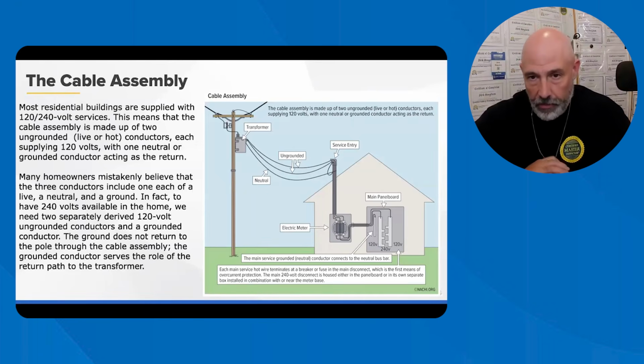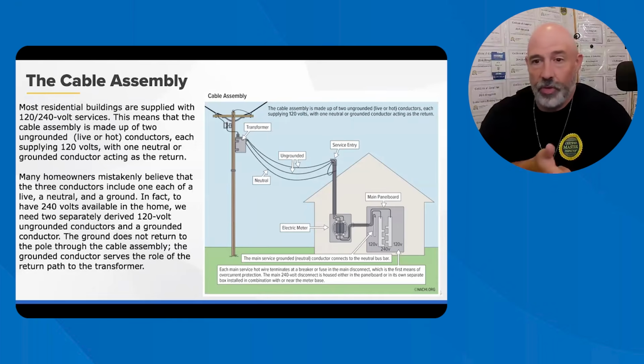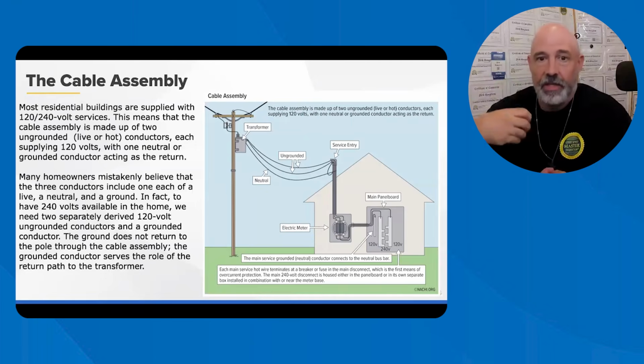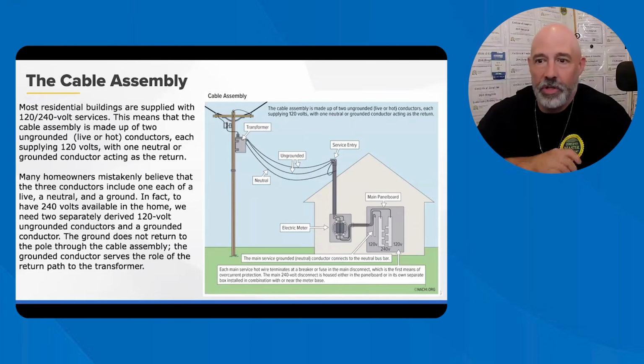It's always going back to that transformer. Now, not the grounding conductor, but the neutral. The hots terminate at the main breaker, and the neutral terminates at the neutral bus.